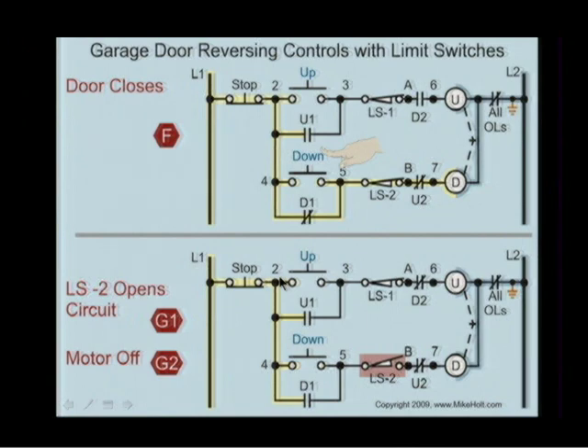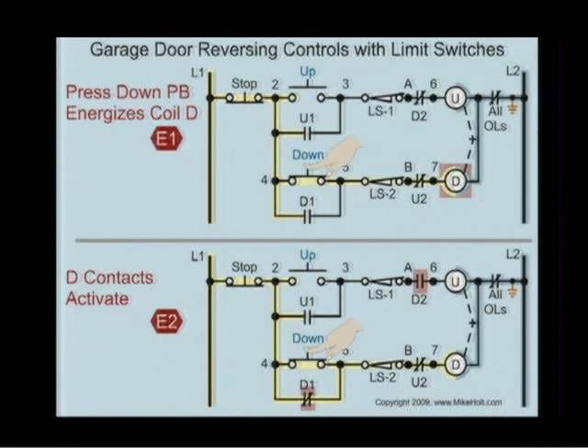Actually, you reverse it, because the photo eye back is only in the circuit when the garage door is coming down, and if something breaks the photo circuit, then the garage door immediately reverses. Oh, you're right. We're not going to stop it. We want it to go back up. All right, help me out here. When I push the down button, I energize this. I would then close a set of contacts to the photo eye to activate that circuit, right? Because it only applies when the garage door is going down. Am I right about that?